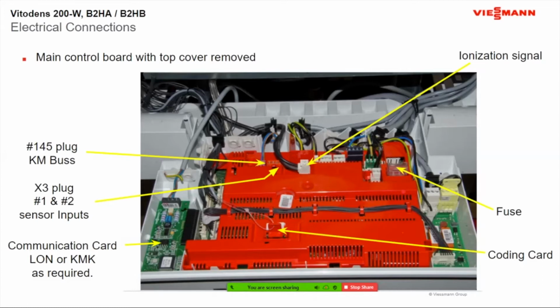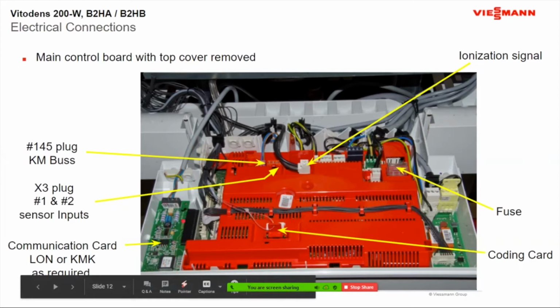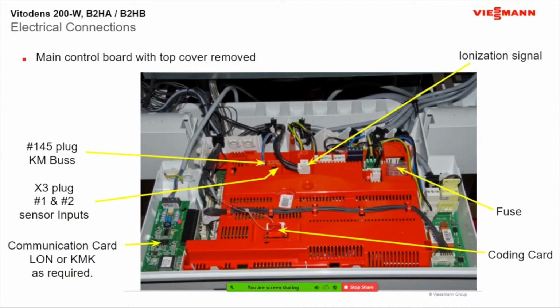There is a spare fuse on the boiler here, so when you slide this piece of plastic out, you'll see in the center of that plastic there's a spare fuse, in case you happen to let the smoke out of the box. On the far left here, you'll see this is where your LON card is going to go. This one actually is showing Viessmann's KMK card, which you could use if you weren't doing building management but still wanted multiple boilers to communicate with each other. But pretty much all of them now are coming with the LON card.